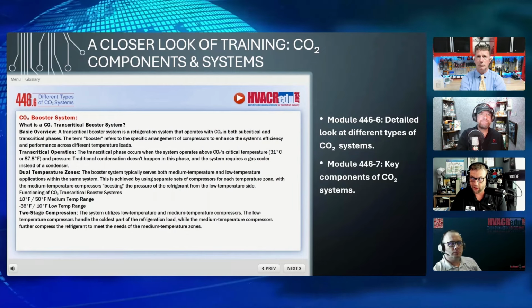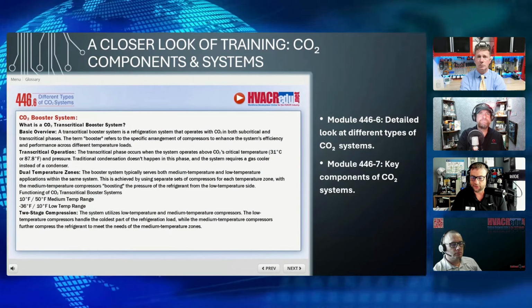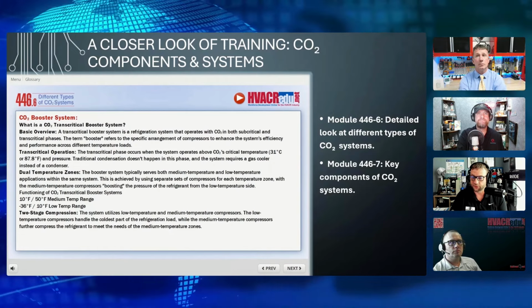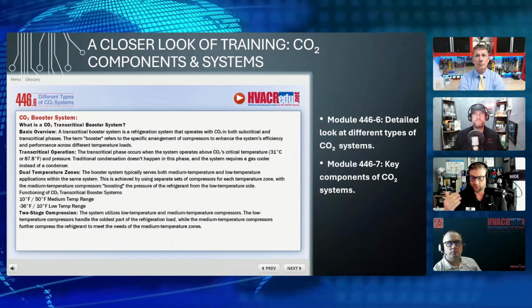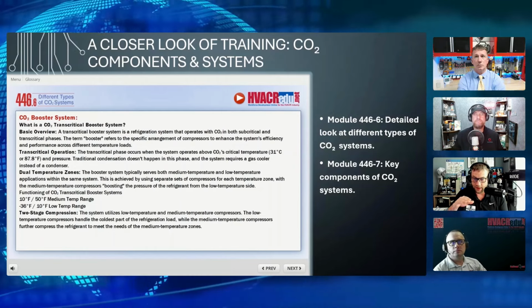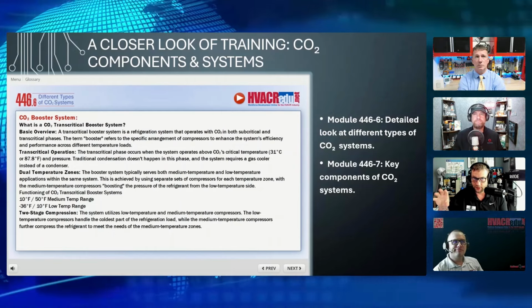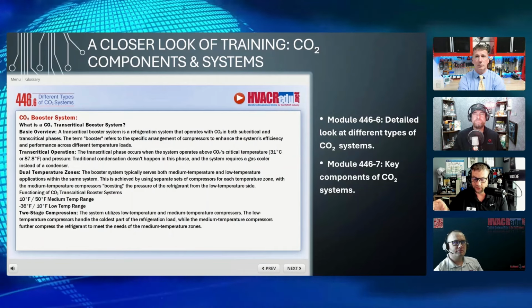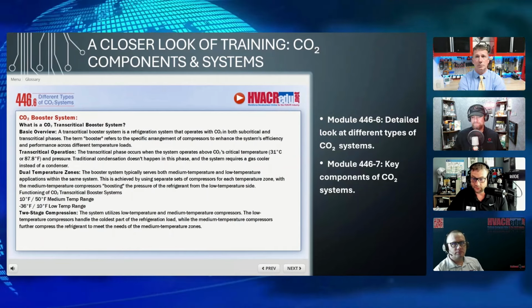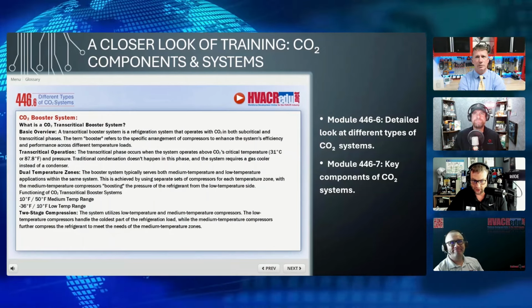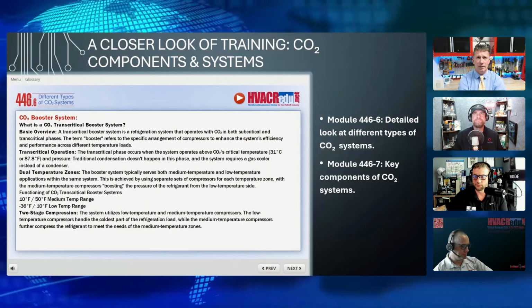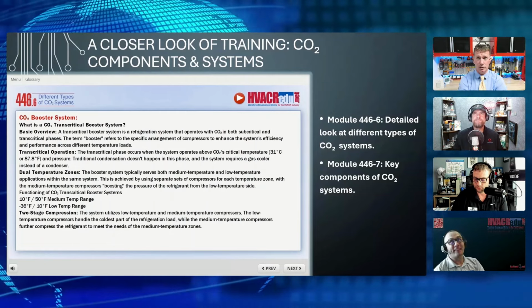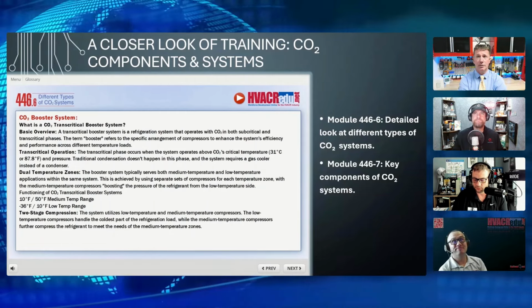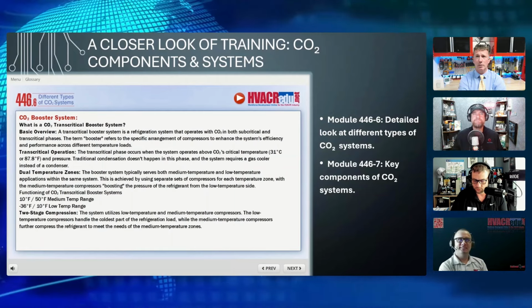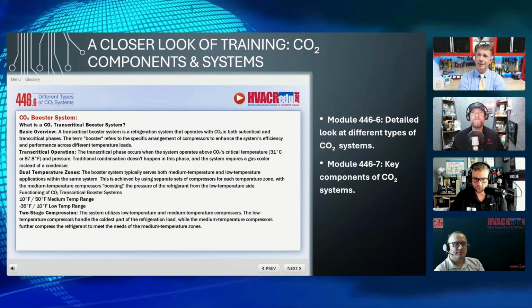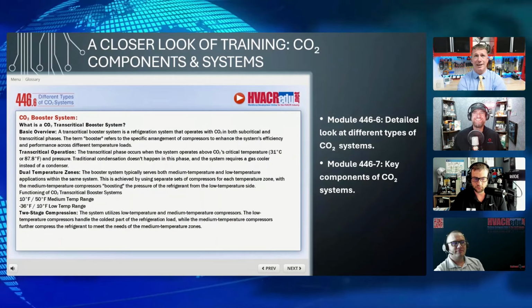For CO2, they have a lot of low TD gas coolers, which only give you a TD of about 5 degrees. So if you're operating at 72 degrees, you're going to operate around 77 degrees. If you have an adiabatic gas cooler, it only has a 5 degree TD. If it's at 82 degrees, you're essentially going to be running transcritical. Yeah, absolutely. A lot of people don't realize that there are critical points for all refrigerants. Most of the time we stay well underneath that. So now we're approaching that critical limit where it doesn't like to jump back and forth between gas and liquid very easily.